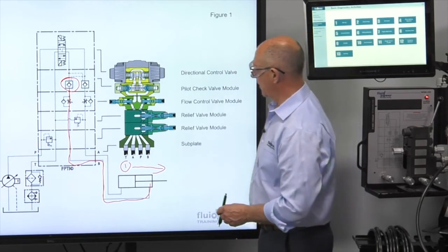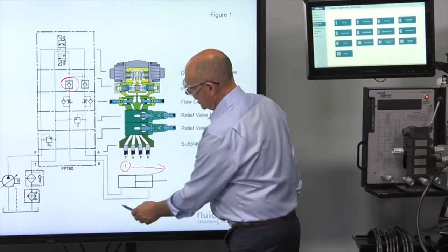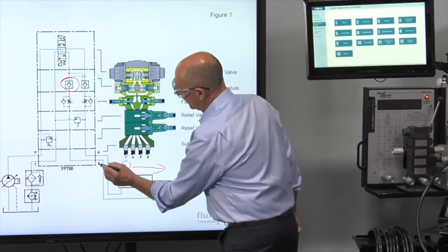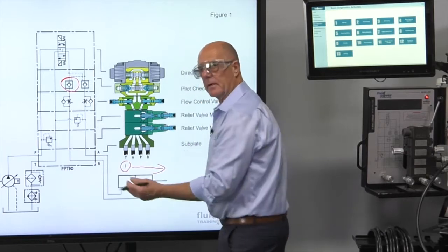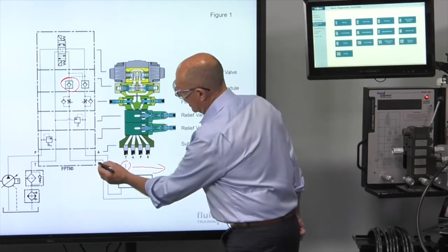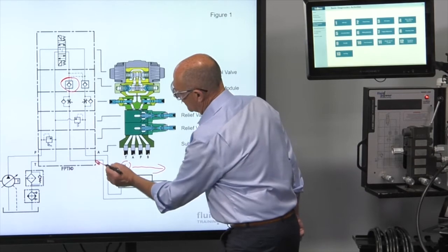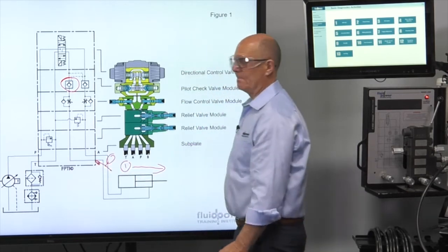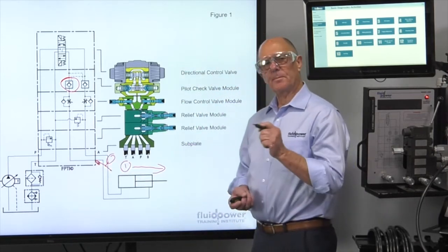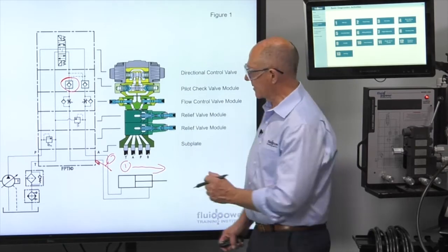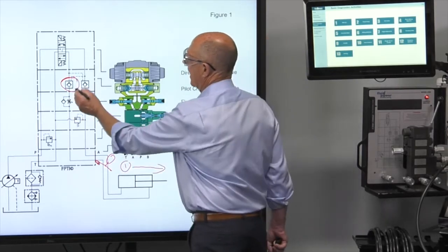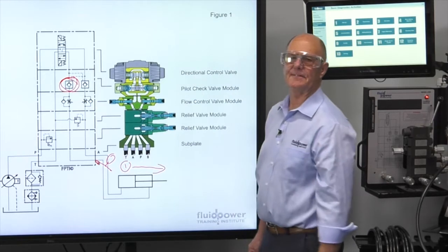All I have to do to test this valve is take my Microleak tester and, again, lock out, tag out, de-energize, verify, and I'm going to hook my Microleak tester up to port B. And I'm going to attempt to pressure up. If it doesn't pressure up, I know for a fact that this valve is defective.